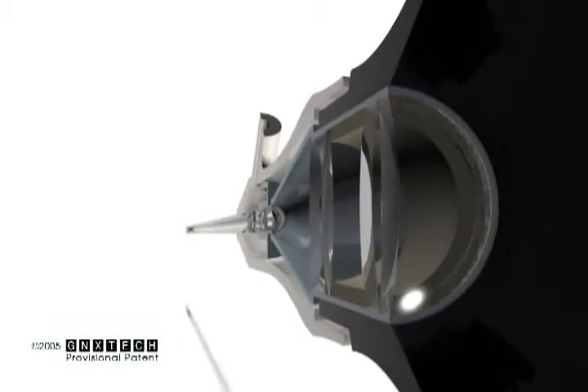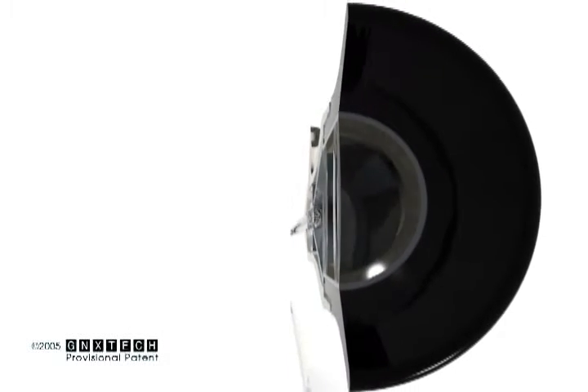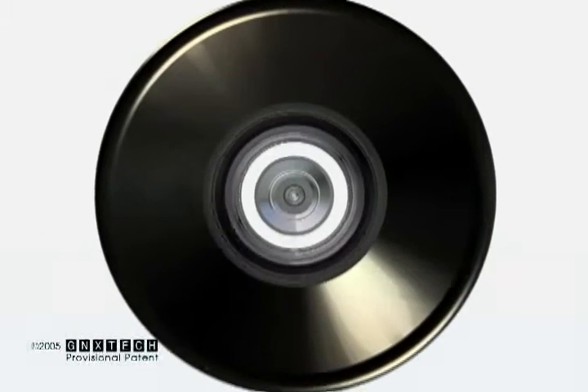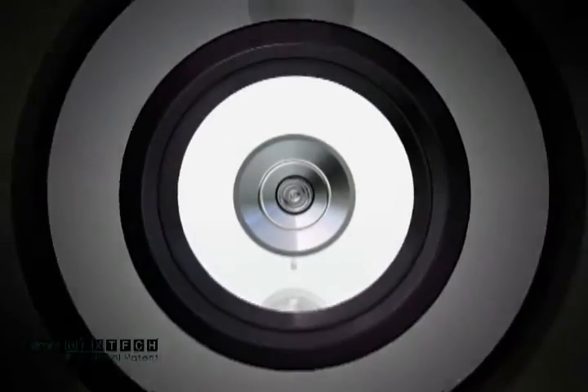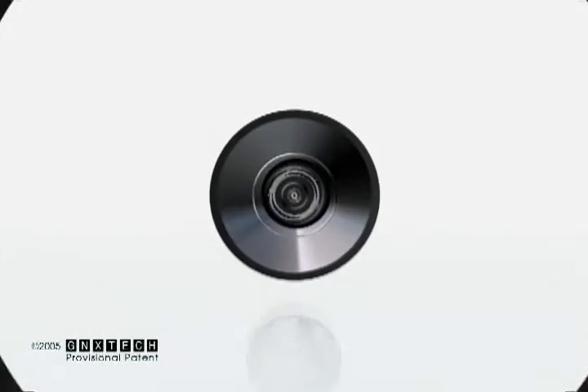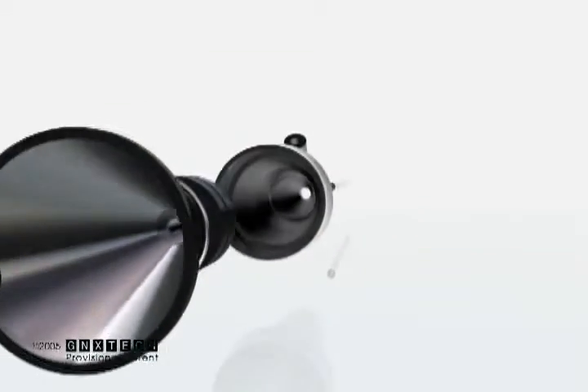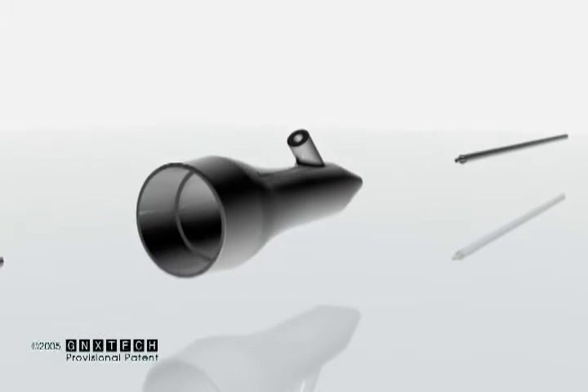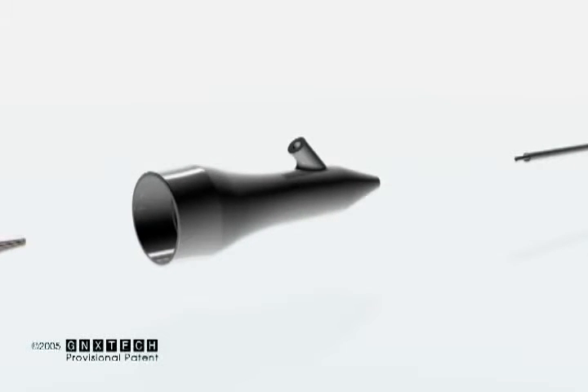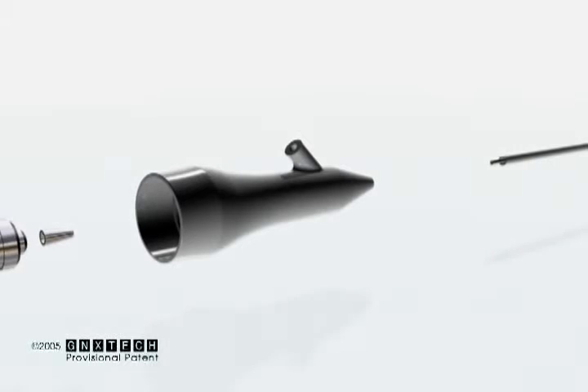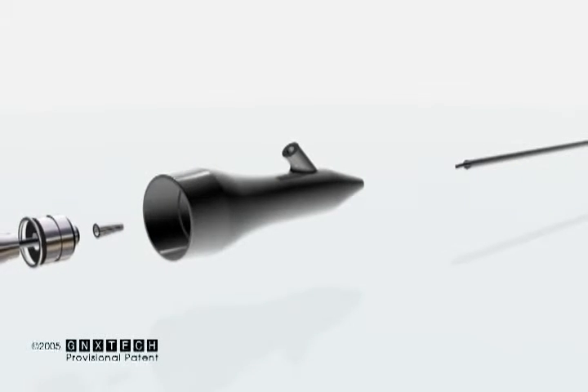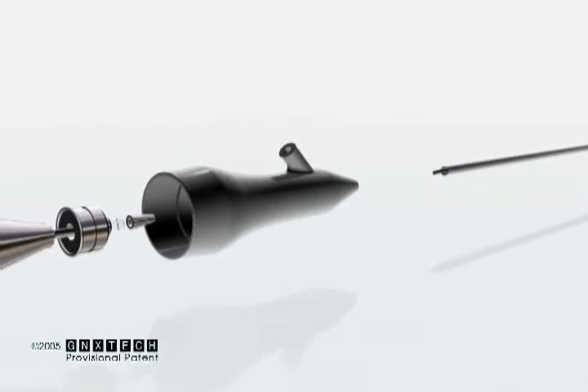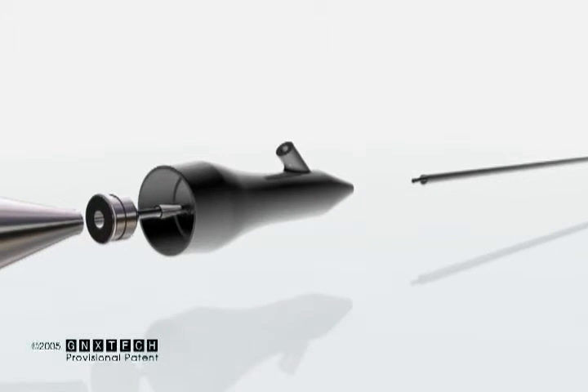To meet both 510K FDA approval for an equivalent device and ease in decontaminating, a flat glass front lens element is permanently sealed inside the 4mm stainless steel tube. Potential contact with a patient is made using only these two materials. The scope's components can withstand 5 megarads radiation exposure, but the preferred method of decontamination is by gas treatment and not by superheated steam or autoclaving.